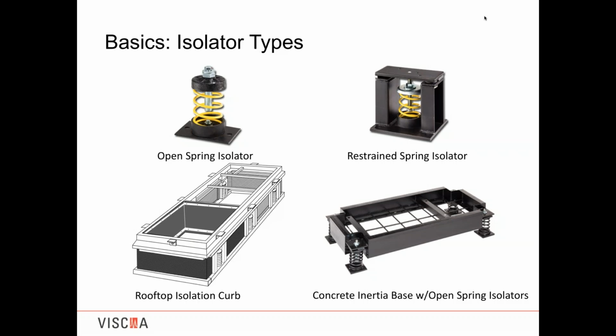All right. Next on the lower left is a rooftop isolation curb. Now curbs are for rooftop, typically air handling equipment. Since the air handling equipment has to move air through holes in the building, it would require some kind of flashable system to prevent water and air leakage into the building. Those would typically have internal vibration isolation, as you can see, such that after it's roofed in, the upper portion of the curb would vibrate and move independently of the lower portion, which is anchored to the building. And those would typically be wind and seismic. You see a lot of the sheet metal ones that come with the equipment. They do not come with isolation. So if you require isolation, you need something other than the sheet metal that comes with the equipment.